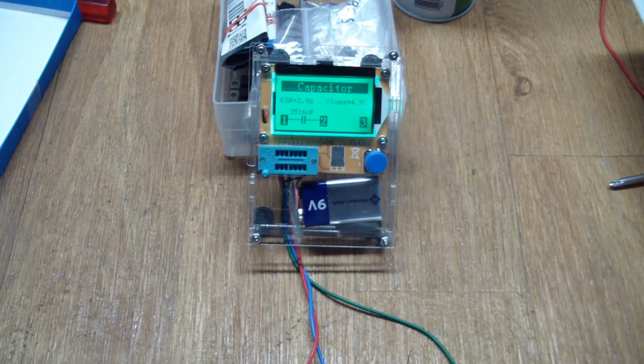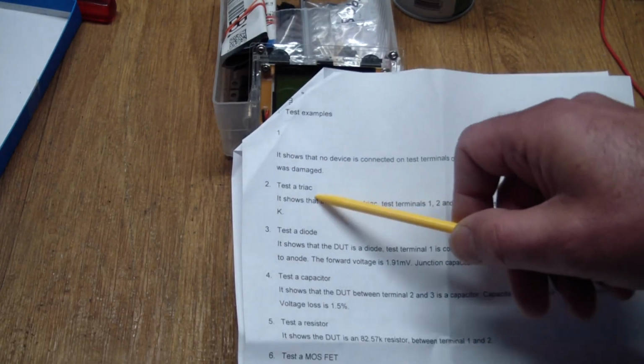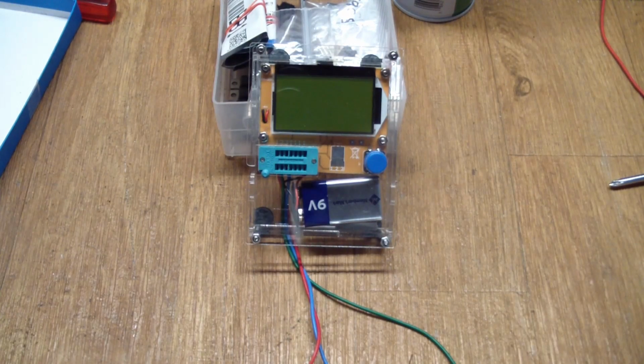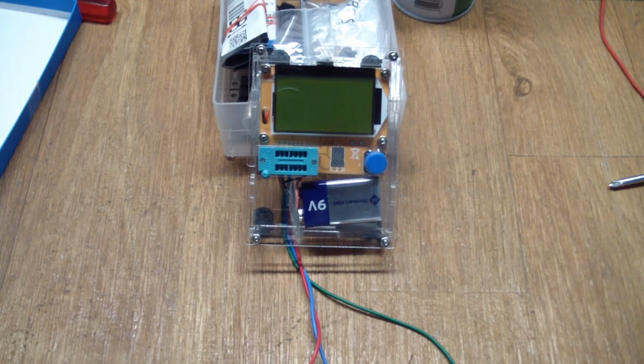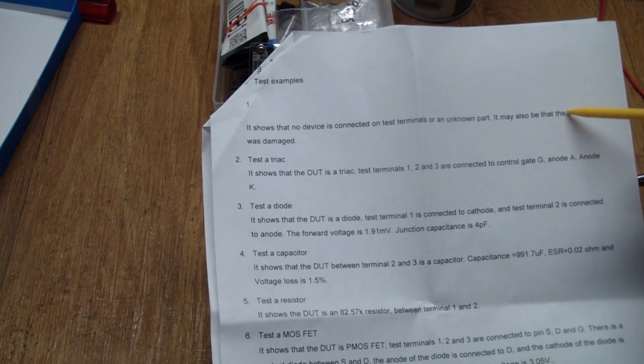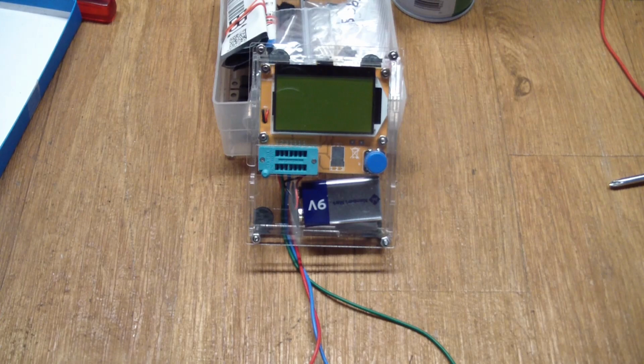So let's run some of the tests. This actually shows us some test examples with pictures of what the screen is supposed to look like, and tells you what to expect. Number one says it shows that no device is connected on the test terminals, or it's an unknown part, or possibly the device was damaged.